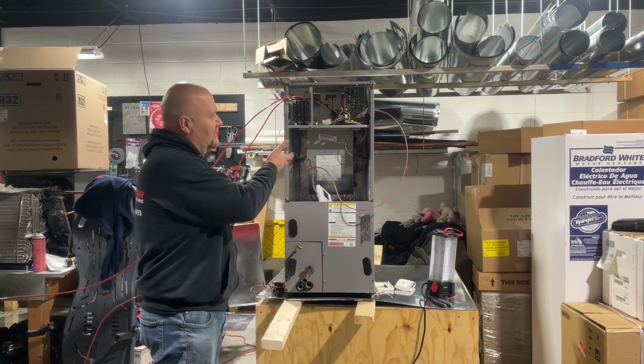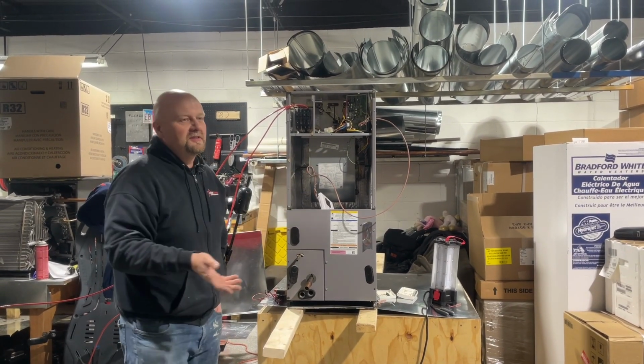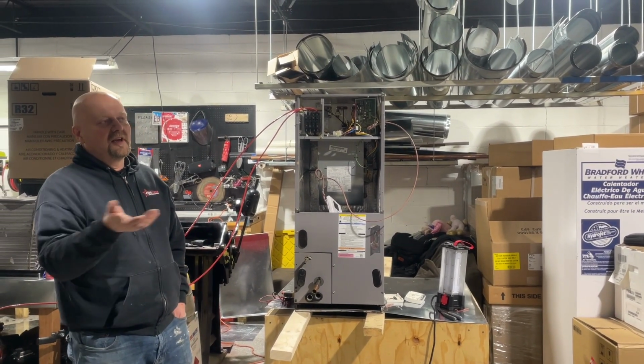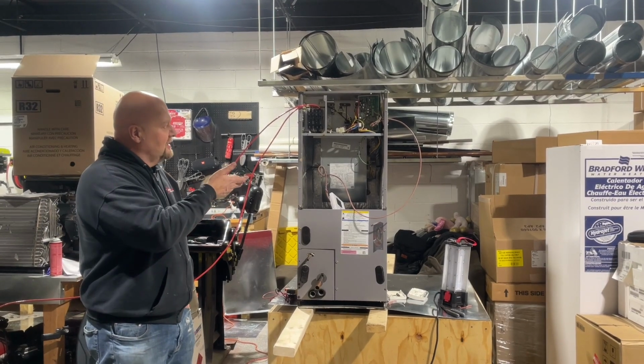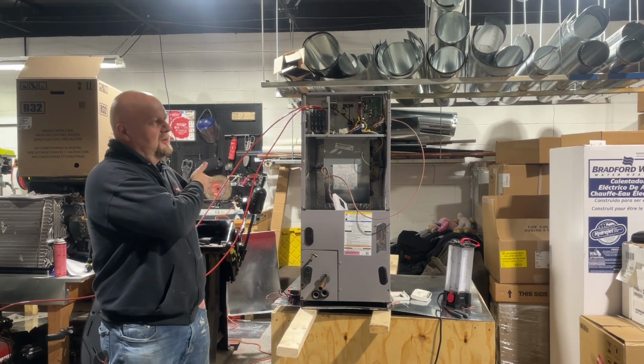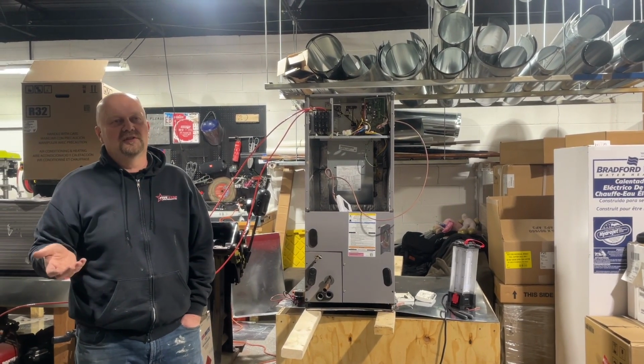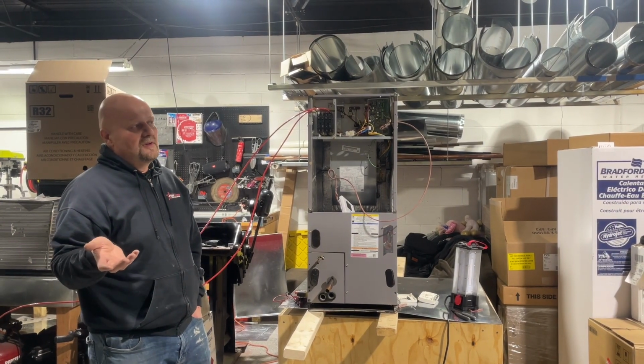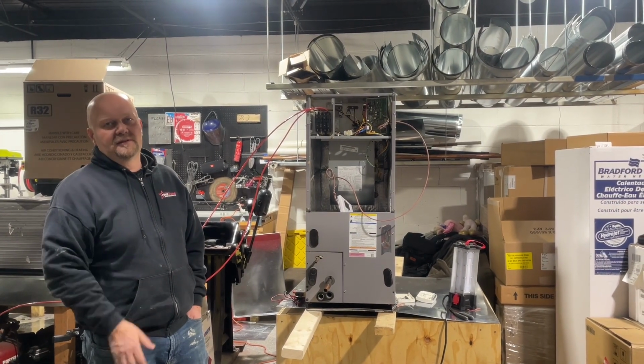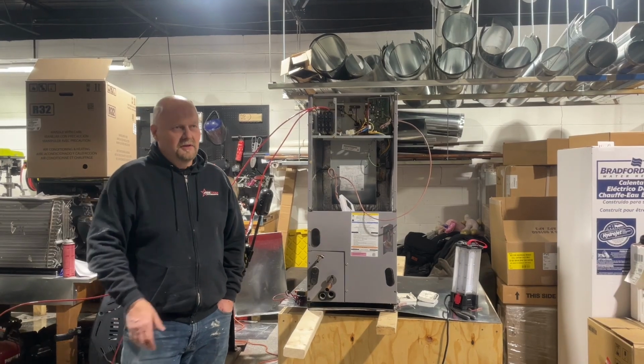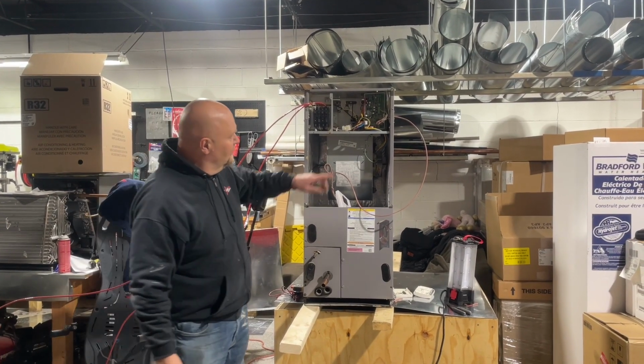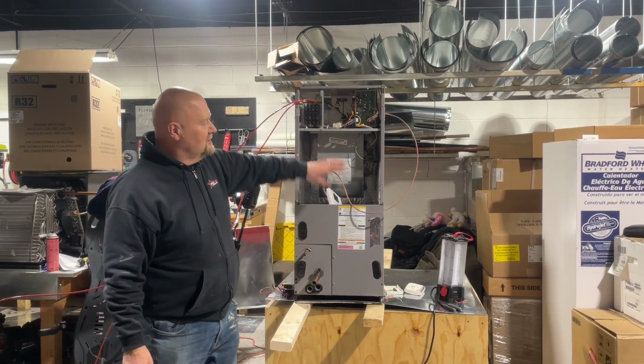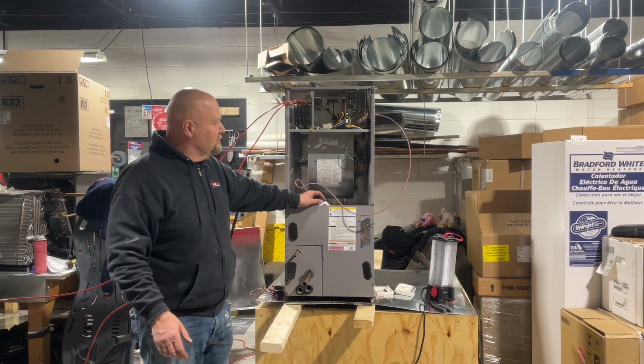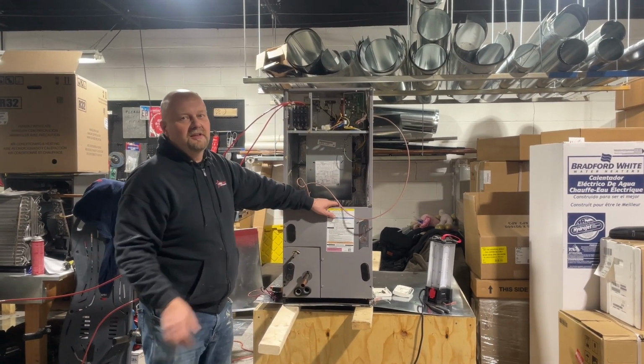If, like, we just figured out that this is a 10 kW system, right? So with a 10 kW system, we were able to actually measure how much wattage was being used. And that's how we would get to that. You'll see it on the nameplate somewhere. It'll always say it on the electric strip, because this furnace is going to come with options. You don't always have to put in a 10 kW.